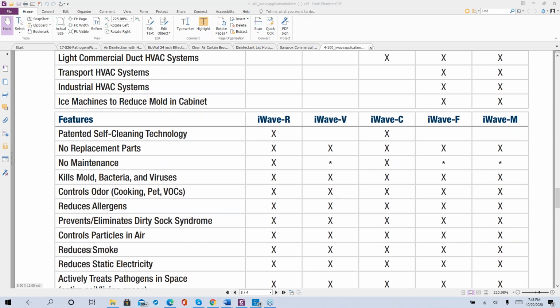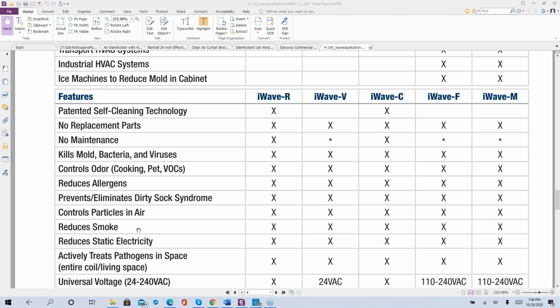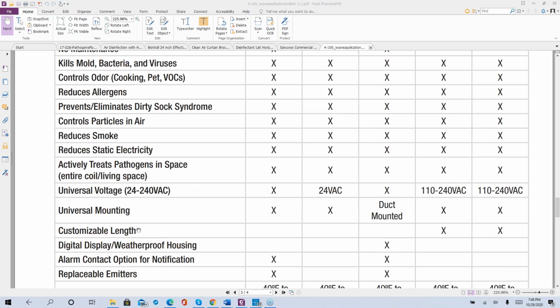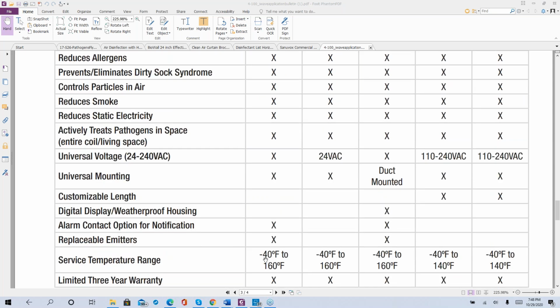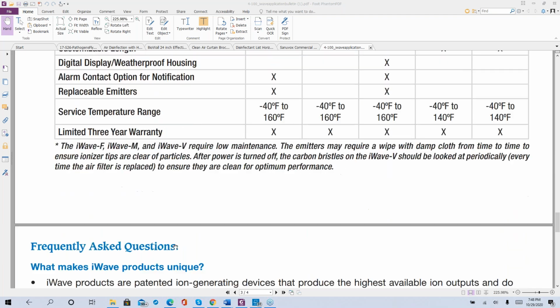So they also kill VOCs, eliminate VOCs, smoke. There's a very interesting video online where they take a glass or a plexiglass, and they've got a cigar and a pneumatic bulb that they pump air through the cigar, creating the smoke. Then they light off the iWave, and literally in 15 minutes, that smoke is gone. It is clear as a bell inside. So it does a great job in that manner. As long as you keep it above -40 and below 160, you're all right. 160, you could get upwards of that on a furnace if you've got it mounted a little bit too close. So use a little bit of discretion as to where you want to mount these.